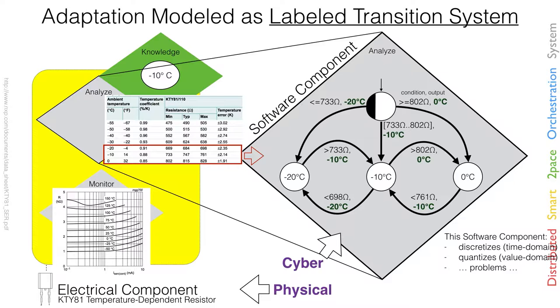As resistance rises above 733 ohms, we take the transition to minus 10; above 802 ohms we reach zero degrees, and if it falls, we go back. Interestingly, the transition upward is at 802 and downward at 761 — this is called hysteresis. We have a range in between to prevent the system from flipping very often, which would produce excessive computational effort on the processor. You can model this entire thing inside a tool — here I modeled the electrical component, showing resistance going up and down on the left and the state machine on the right.